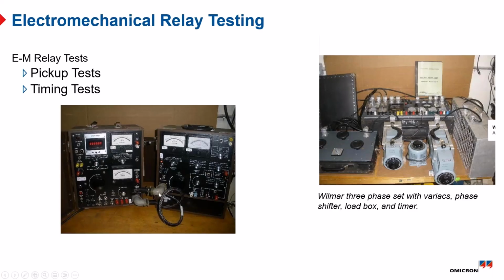Here we got a little later implementation of the purpose-built test set, and here on the right, this is a variac and load box set up for testing an impedance relay, probably from the 50s and 60s time frame. But as you can probably imagine, hooking these things up to electromechanical relays, it's basically an entire table worth of stuff. The level of knowledge that was required to be able to set these things up and test them and adjust these things and get them back into service is admirable, especially without the modern tools that we have today. But you can imagine, relay techs back in the day, you're part watchmaker, part electrician, part engineer to get these things actually working.